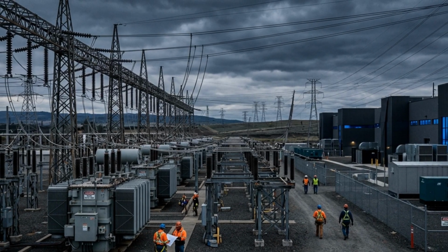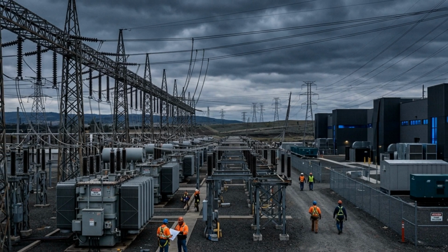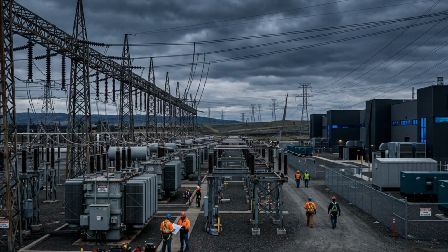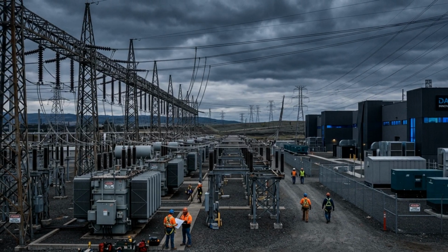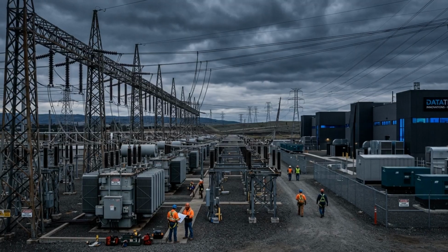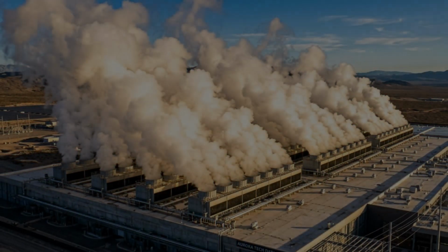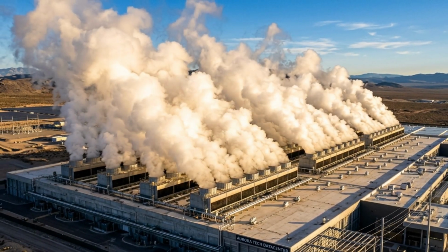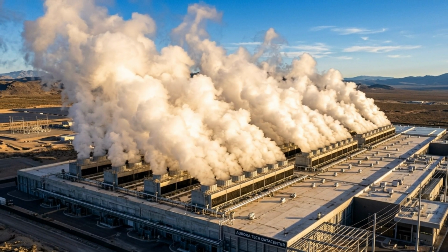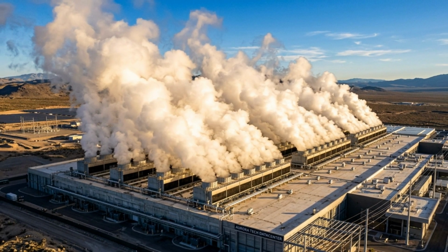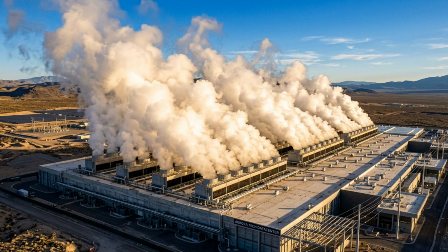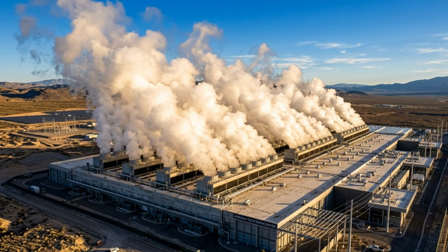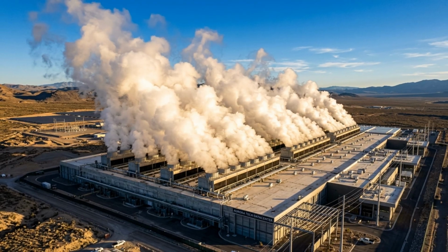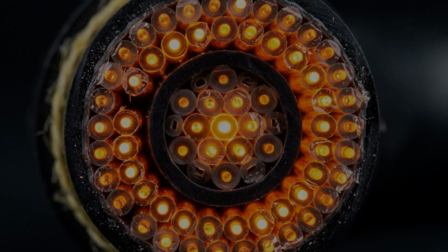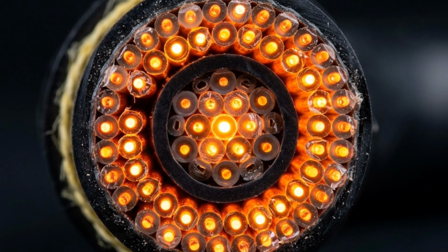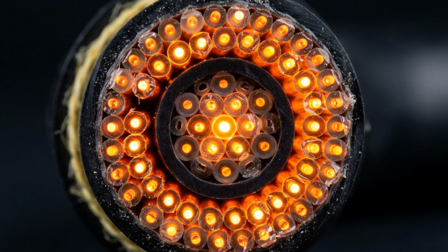This is where liquid cooling has become absolutely essential. There are several approaches. In direct liquid cooling, cold water or a water-glycol mixture flows through tubes or cold plates in direct contact with the chips themselves. The liquid absorbs the heat and carries it away to a heat exchanger, where it transfers to the building's broader cooling loop. Some facilities are experimenting with immersion cooling, where entire servers are submerged in tanks of electrically non-conductive fluid. The fluid boils at low temperatures, carrying heat away through phase change, then condenses and cycles back down. This approach is extraordinarily efficient, but it requires custom hardware and operational procedures that most data center teams are still mastering.